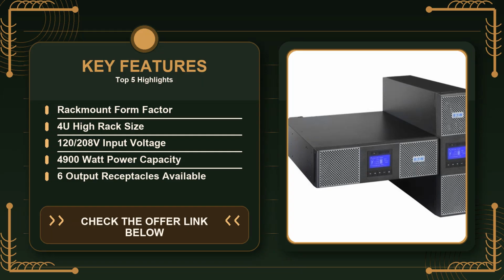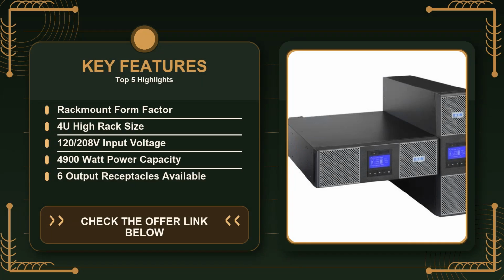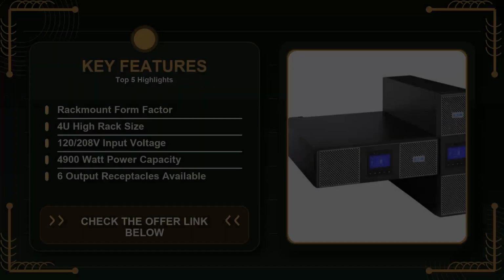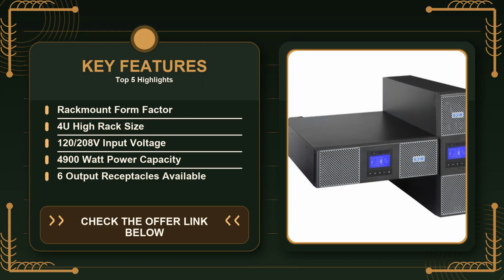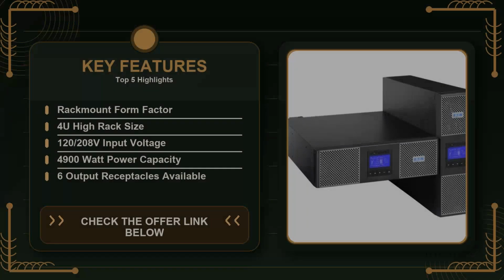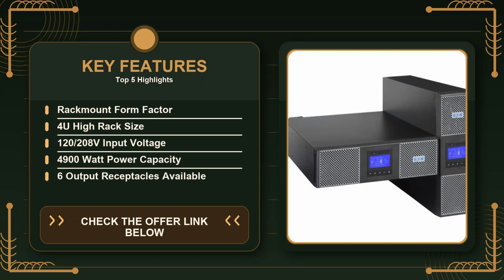The output receptacles are also a mix of IEC-C13 and NEMA 5-15, giving you a little more versatility than a UPS that only offers one plug type. This makes it easier to power both rack-mount equipment and peripheral devices such as a small UPS-compatible monitor or a test server that you might keep on a bench.